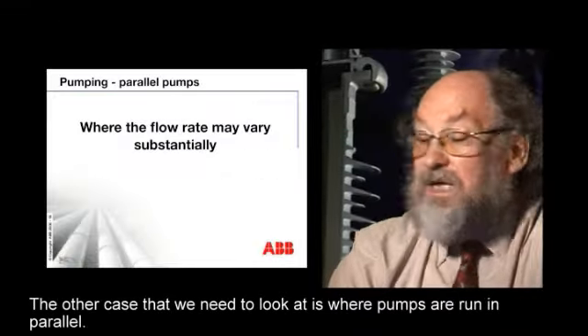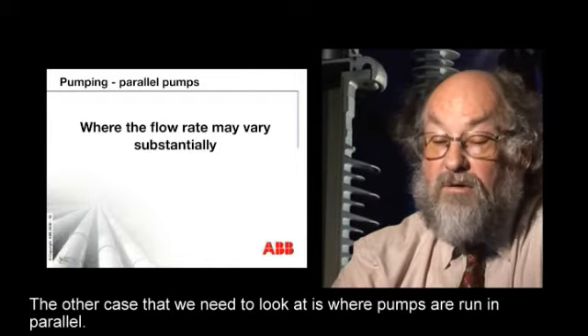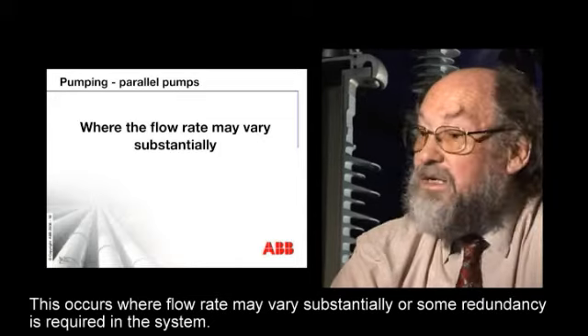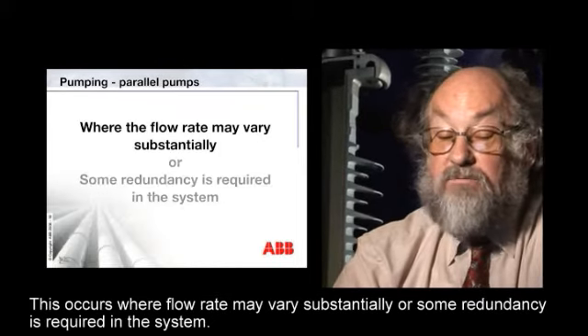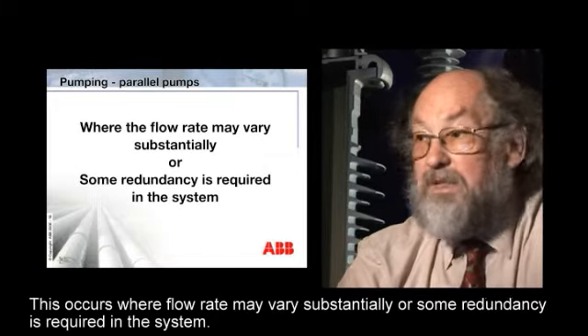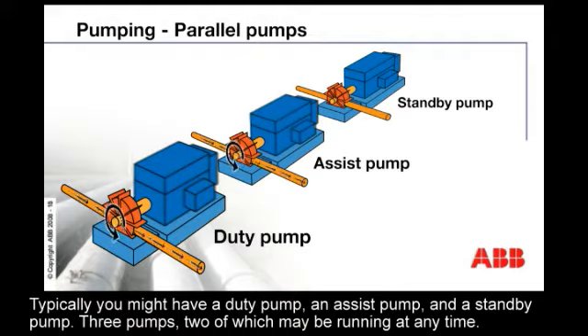The other case that we need to look at is where pumps are running in parallel. This occurs where flow rate may vary substantially or some redundancy is required in the system. Typically, you might have a duty pump, an assist pump, and a standby pump — three pumps, two of which may be running at any time.